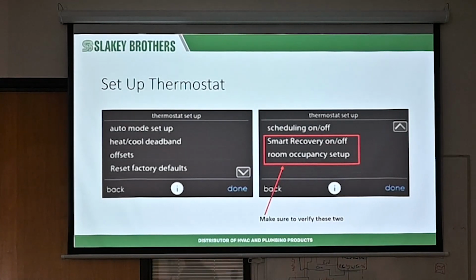Either way, if the controller's over here in the living room where the party's happening and nobody's walking up and down that hallway, if that room occupancy is on by accident and it doesn't sense any movement, it's going to shut the unit off. It won't work. Doesn't matter what programming you put on there. So honestly, that's why they ship these now off, but just double check it, make sure it's off. Smart recovery, on or off. Make sure it's off as well, because it usually creates a problem.